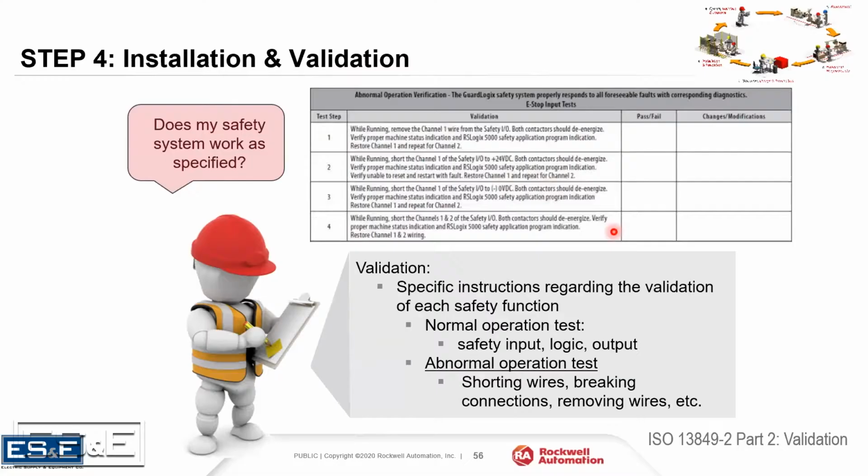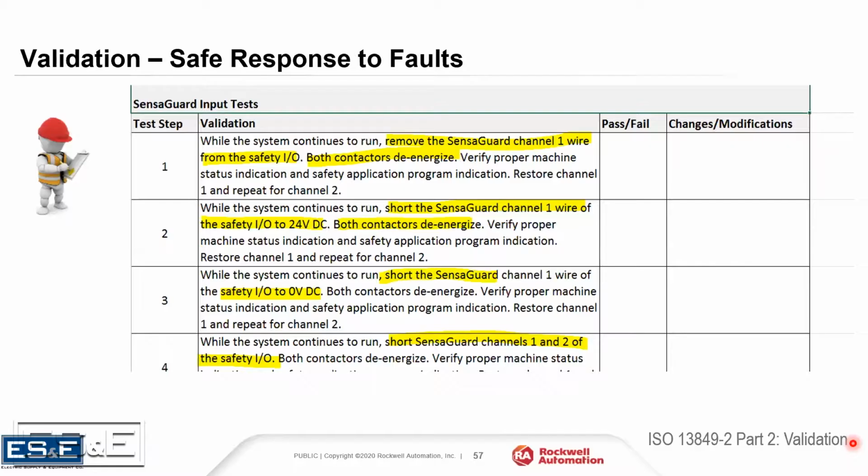And so then we're at step 4 at this point, the installation and verification and validation piece of it, which again, it's important that this is documented. In your documentation you see an example of what that might look like, and it really should be a step-by-step test procedure, telling them exactly what they need to do to make sure that the components and the circuit we have in place truly will respond the way we need them to when we have faults in the circuit.